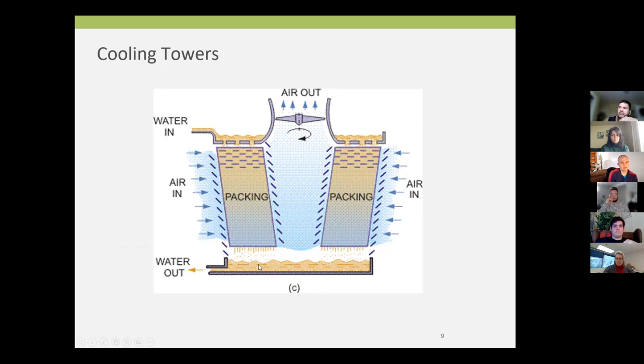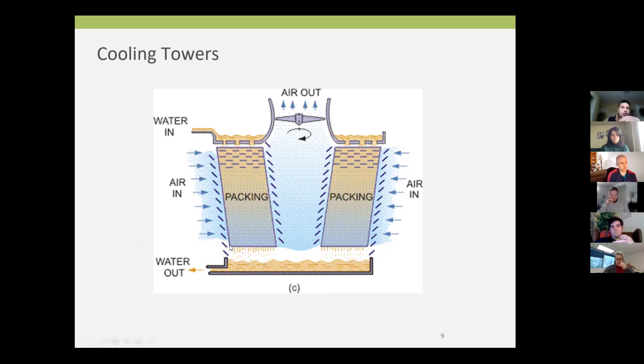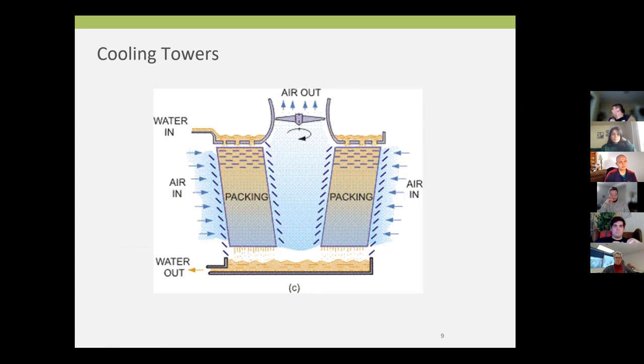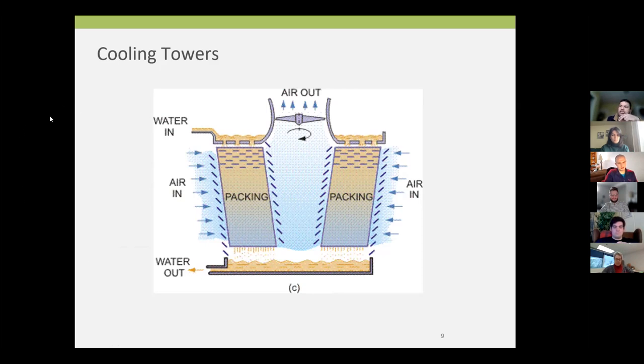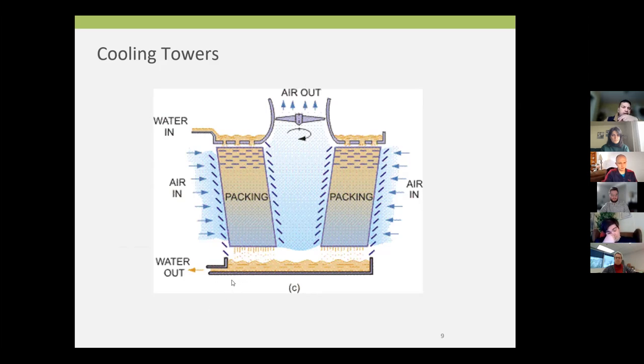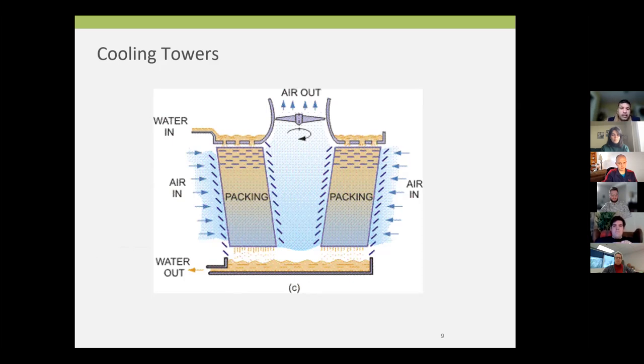You all see those plumes of clouds when you drive past the refineries in Salt Lake. Everyone is talking, oh, that looks like fumes. Well, those big plumes are nothing but vapor. The real toxic stuff, you can't see. That's the stuff coming out of the higher chimney stacks. So that plume is over here. That's what you're seeing, that big white cloud. Air goes here. This remaining water that did not evaporate comes down in the sump, and it's cool. It's cool as cold as the wet bulb temperature. Theoretically, the coldest this water can get is the wet bulb temperature. Now, of course, in reality, nothing works to theoretical efficiency, so it tends to be a little bit warmer than the wet bulb temperature.